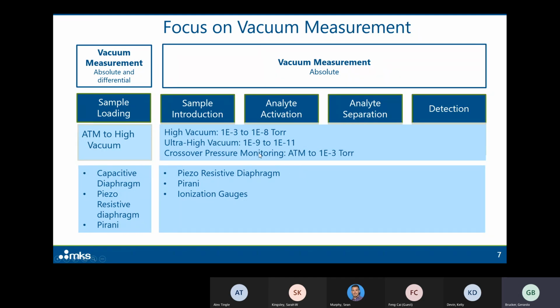But also keep in mind that at some point you have to pump these systems down, right? At some point, the analyte separation building block will be at atmosphere, because maybe you service the machine, maybe you do the PM, whatever it is. So you're going to pump it down. It's very common that the gauges in every one of these building blocks will include measurement all the way from atmosphere down to 10 to the minus 8 torr or 10 to the minus 11 torr, whatever it is, because you want to be able to track the entire pump down from atmosphere down to the base pressure or the ultimate pressure of operation of that section. So this is a piezoresistive diaphragm type technology.